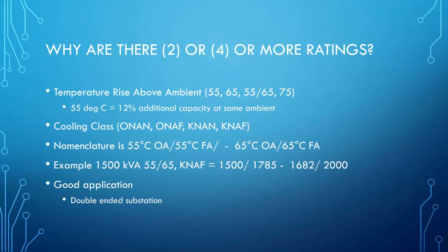There are some customers who, I believe, specify 55 degrees C temperature rise. They specify it because I believe at one point the standard was 55 degrees. A 55 degrees C transformer is going to give you about a 12% additional capacity. Now, what does that get you?